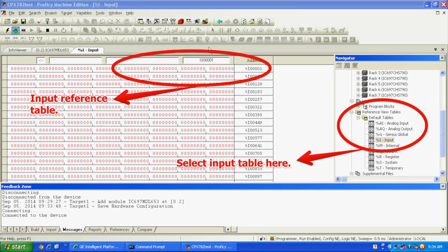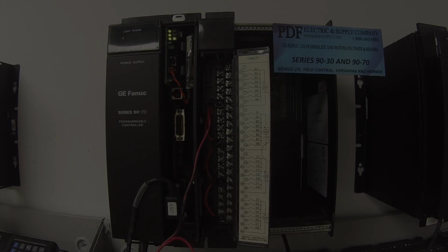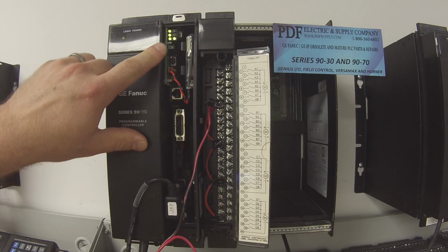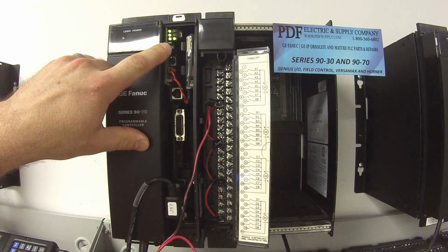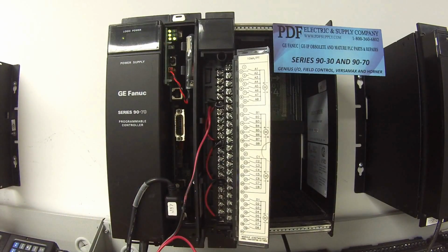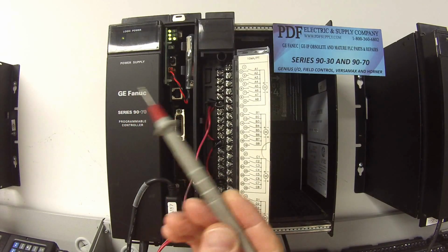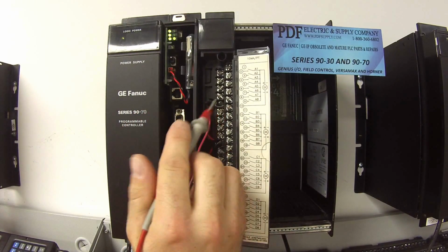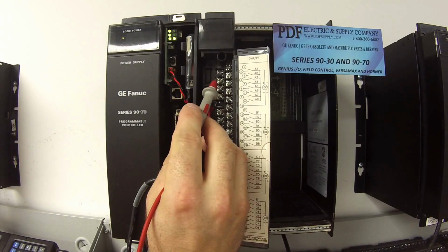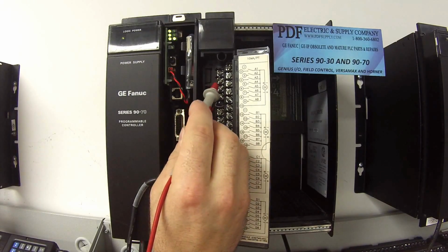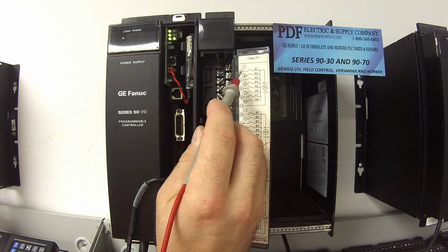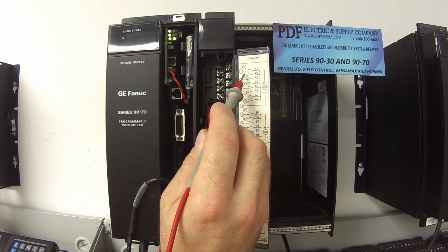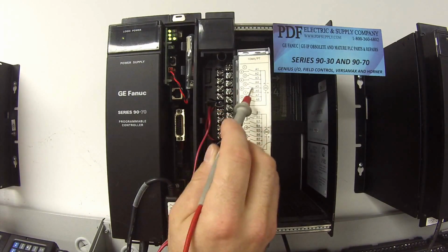This is just a discrete input, so it's just on or off. The CPX is in run mode right now, and this is a working system. I'm going to take my positive probe lead and start touching it to the corresponding terminals. Terminal number 2 is channel 1, terminal 3 is channel 2, and so on.